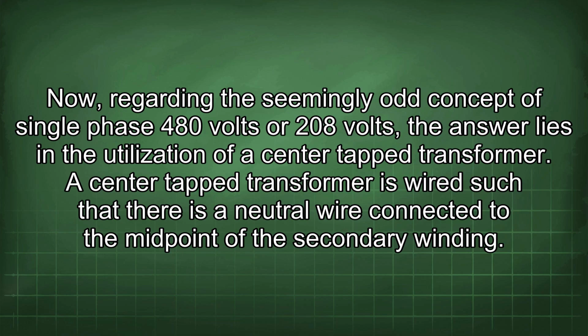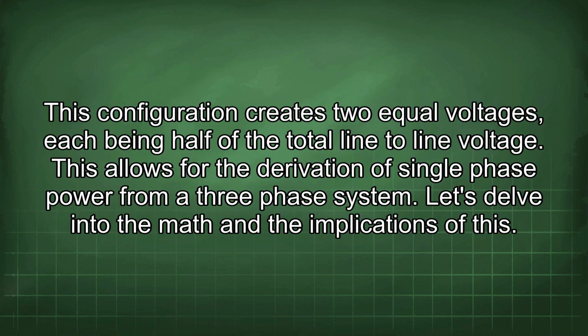Now, regarding the seemingly odd concept of single-phase 480 volts or 208 volts, the answer lies in the utilization of a center-tap transformer. A center-tap transformer is wired such that there is a neutral wire connected to the midpoint of the secondary winding. This configuration creates two equal voltages, each being half of the total line-to-line voltage. This allows for the derivation of single-phase power from a three-phase system. Let's delve into the math and the implications of this.